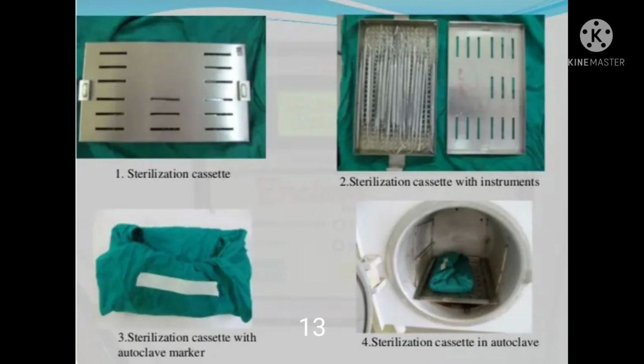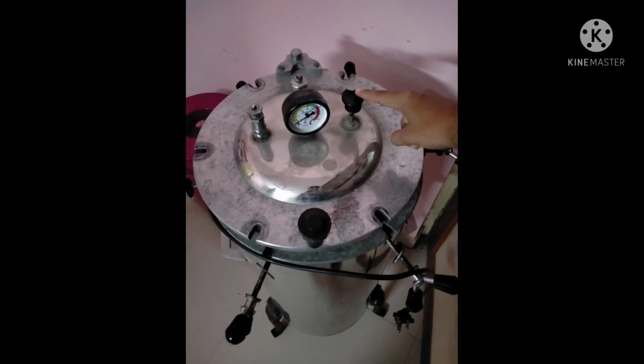These are basically placed on an autoclave tray. It must be kept in mind that the instruments should not be mixed with one another during autoclaving because the sharp and delicate edges of instruments can get damaged. So the instruments are properly kept in the matrices provided in the autoclave box, and the drum should not be loaded fully. There should be some space for the steam to get around. So the take-home practical message is: get the autoclave ready. Always use distilled water or at least RO water for autoclaving. Get all instruments and linen packed. The drum should not be too loaded.